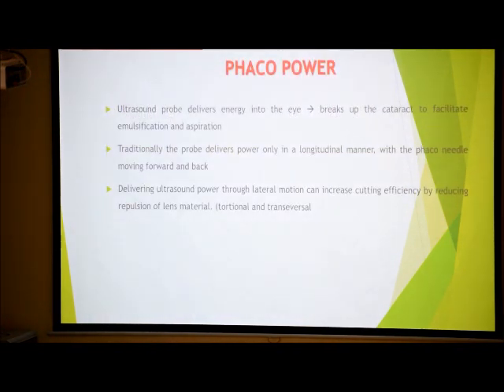So come to phaco power. Phaco power is the ultrasound probe delivering energy to the eye, breaking up the cataract to facilitate emulsification and aspiration. Traditionally, the phaco probe delivers power only in a longitudinal manner, but the newer generation phaco machines have transverse rotation movements, called torsional phaco, which is much more efficient than the traditional one. Delivering ultrasound power through lateral motion can increase the cutting rate and reduce repulsion of lens material, and that increases the overall efficiency of the machine.